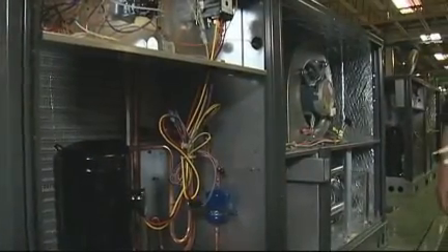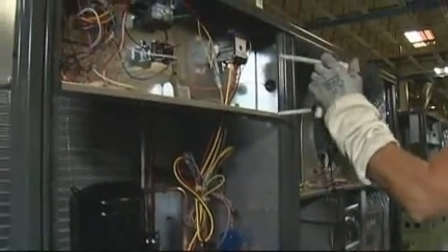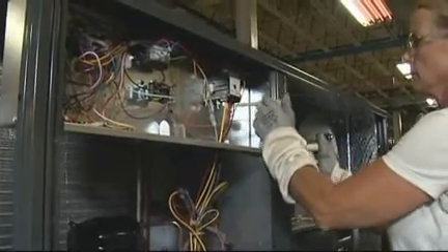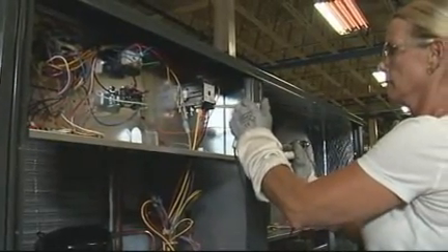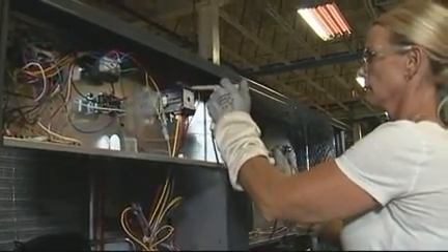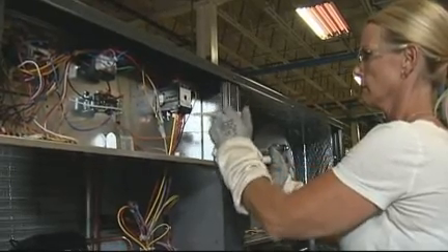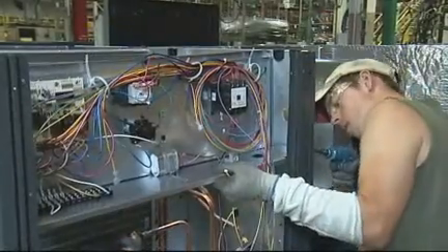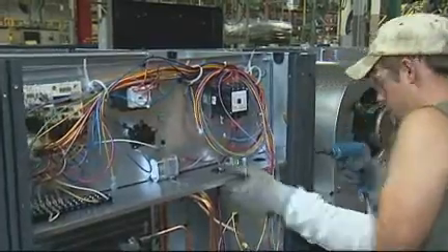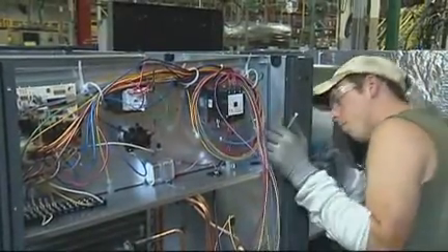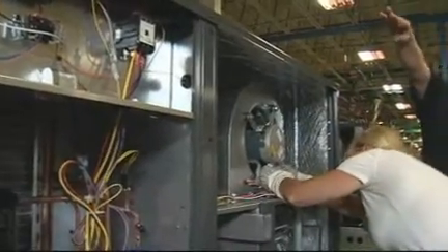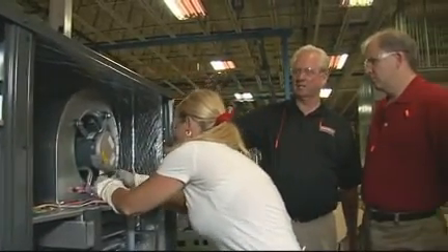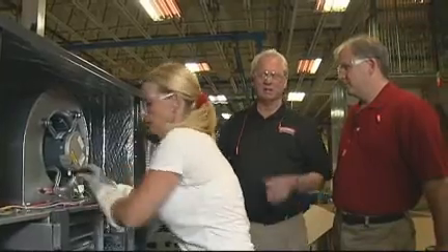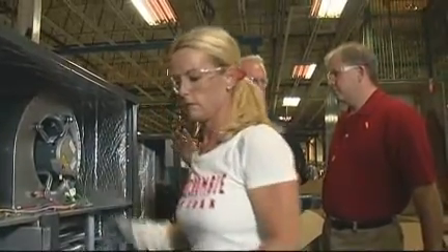Okay, Mark, we're at the run test station, and this operator is our run tester. Right now she's doing a high pot test, which is a high voltage, low current test to make sure there's no loss to ground. There's no shorts in the unit anywhere. When we did our customer research, single side servicing was very important. What I mean by single side servicing is, you see, you got the control panel on this side, you got the compressor on this side, you got the blower motor on this side. Everything can be done from one side of the unit.